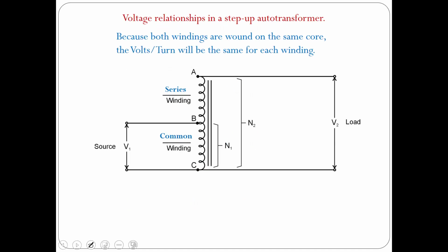Okay, so the voltage relationship in a step-up autotransformer. Because both windings are wound on the same core, they still have the same volts per turn for each winding. So let's say that in this step-up autotransformer, we had a 240 volt source. And in the common winding, so from here to here, there was a total of 480 turns. We could figure out the volts per turn. So 240 divided by 480 turns gives us half a volt for every 1 turn. Well, that same half a volt per 1 turn is what's on the series winding here too. Okay, so whatever is established there is what it's going to be on the series winding as well.